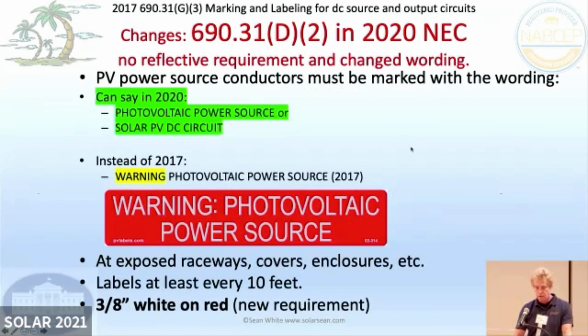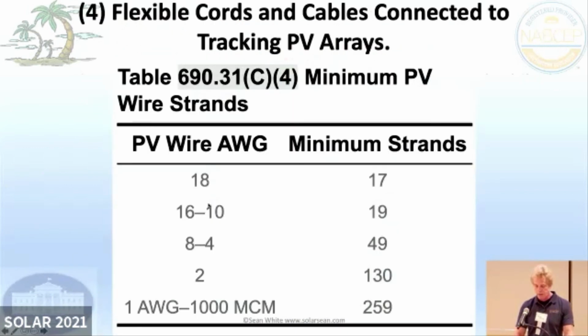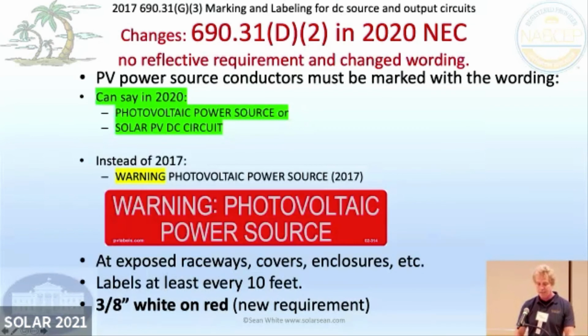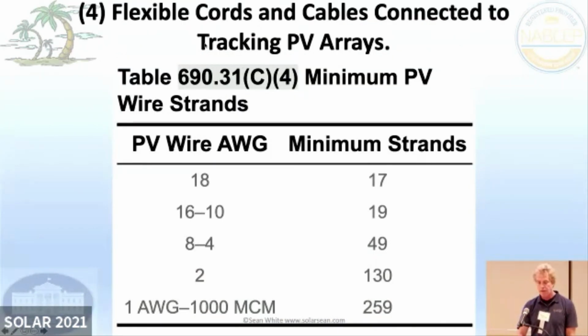Small changes too with this sticker every 10 feet on your circuits and at junction boxes and things. Now you can put fewer words. It doesn't have to say warning on it, and it doesn't have to be reflective. I think this probably has to do with people being more used to solar, and the rapid shutdown makes it safer, so this is a little bit less severe. It doesn't have to be a reflective label, and it doesn't have to say warning. And this is also only for DC. Some inspectors used to make people put it on their microinverter circuits. Remember that? I always thought this was confusing.